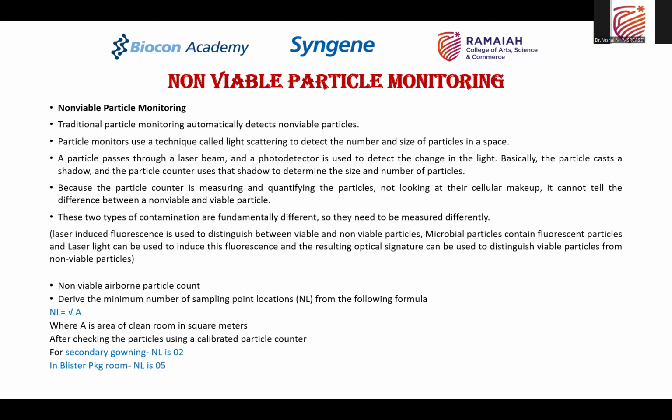When fluorescence is induced in the viable cells or particles, the optical signature which is developed allows the instrument to detect the viable and non-viable particles in the area. So basically, the light scattering systems are used for counting the non-viable particles.